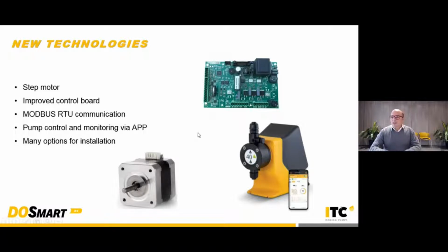What are the newest things on this pump? This pump is based on a step motor. This gives the pump very special characteristics regarding the control and the operation of the system. It has an improved control board to guarantee that everything runs smoothly. In the same line as our latest products, the DOSmart pump has communication through Modbus and can be controlled and monitored via our app. In addition, to help the installation of this pump, we have supplied many options for installation. Let's go a little bit deeper on this.